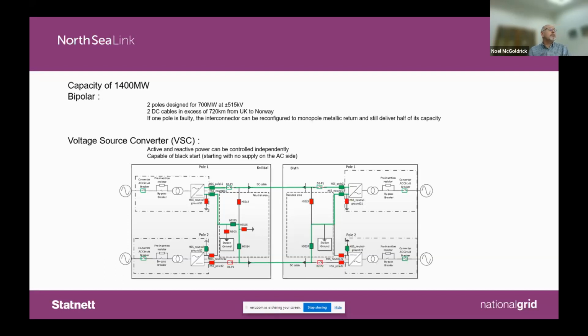So we've gone for a bipole arrangement, shown here with two cables: one DC cable operating at plus 515 kV and the other at minus 515 kV. We've gone for a voltage source converter, different from older current source converter technology. Because we have a voltage source converter, we can generate our own voltage waveform, either lagging or leading the system volts, allowing us to generate or absorb reactive power as needed.